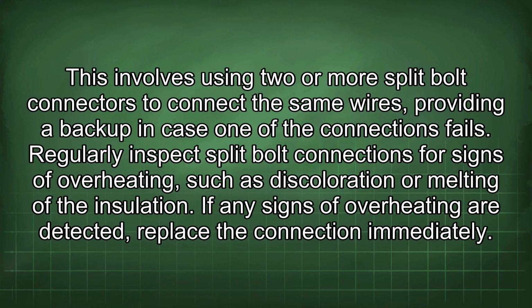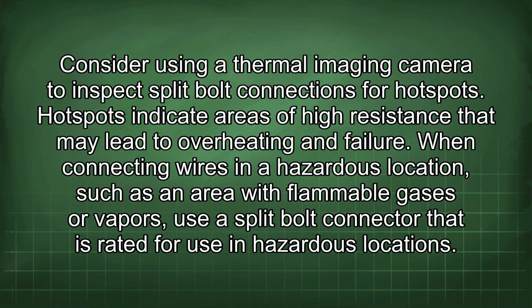Regularly inspect split bolt connections for signs of overheating, such as discoloration or melting of the insulation. If any signs of overheating are detected, replace the connection immediately. Consider using a thermal imaging camera to inspect split bolt connections for hotspots. Hotspots indicate areas of high resistance that may lead to overheating and failure.